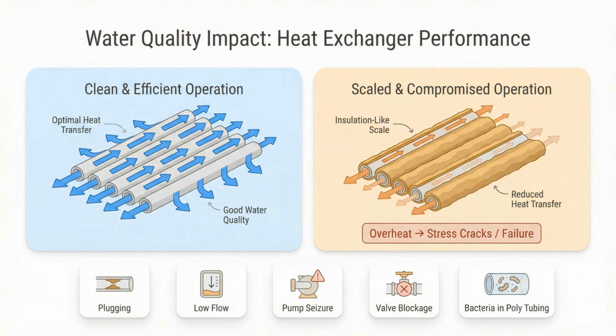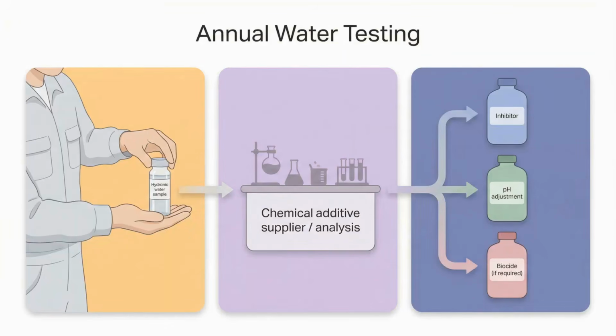Contamination can also plug tubing and circulators, causing low flow and overheating, and some polytubing systems can even support bacterial growth that reduces performance. The recommended practice is yearly water checks, with chemicals added as required. A water sample can be taken to a company that analyzes hydronic water and supplies the right treatment chemicals. The point is reliability and efficiency. Proper testing and treatment prevents corrosion, scaling, and the cascade of component failures that follow.